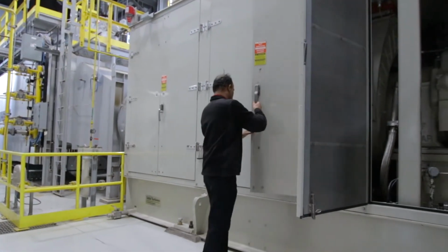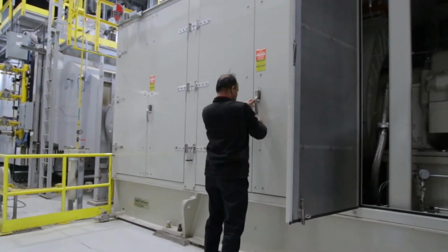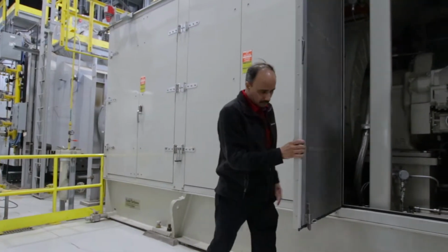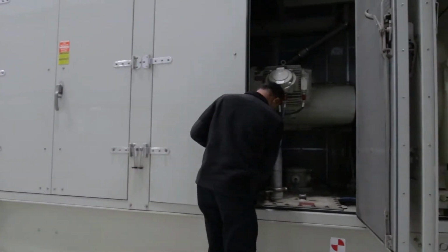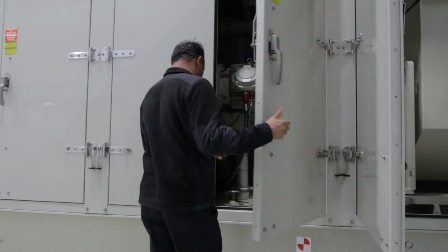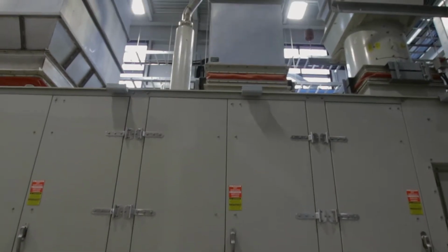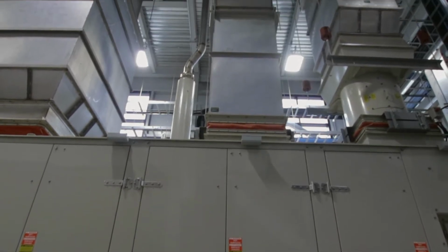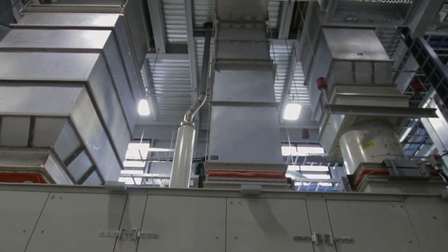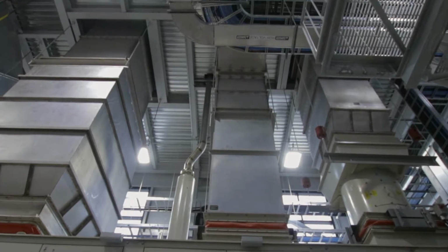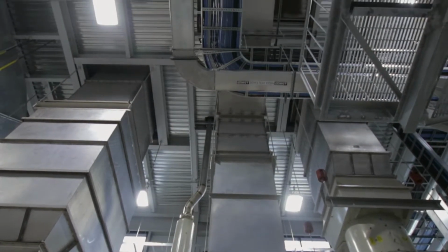It's really part of a broader cogeneration system. It has all the ductwork, all the lube oil coolers, all the MCCs, all the VFDs, all of that is part of this complete package. The system has been designed, whether it be the gas turbine package or the transformer or all of the ancillary systems, so that at that overhaul point, it also could go to a larger machine. So instead of 4.5 megawatts, you could put in a 5.5 megawatt machine and make more power out of this gas turbine.